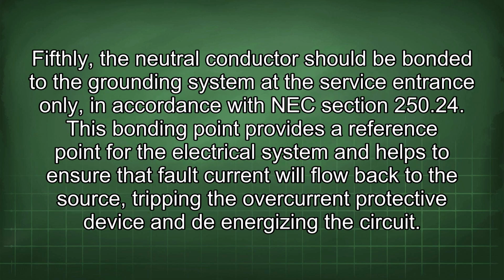Fifthly, the neutral conductor should be bonded to the grounding system at the service entrance only, in accordance with NEC section 250.24. This bonding point provides a reference point for the electrical system and helps to ensure that fault current will flow back to the source, tripping the overcurrent protective device and de-energizing the circuit.